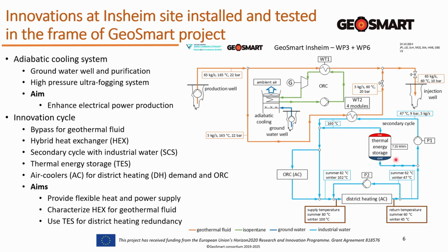In addition, you can see a thermal energy storage with a hot side and a cold side. This is always filled with liquid. When we want to charge it, hot water is pushed in from the top, and a thermocline establishes, so we can store the hot water by pushing the cold water out of the storage. If we want to discharge it, it's simply the other way around: we feed in cold water and push out the hot water to supply district heating or the organic Rankine cycle.